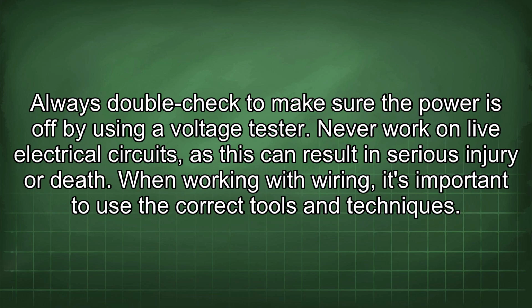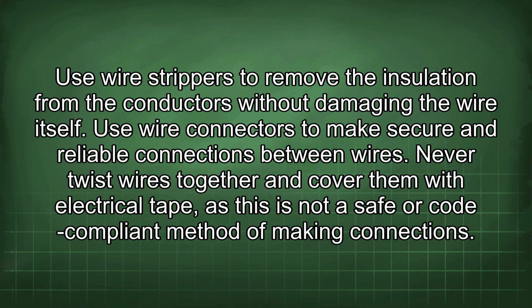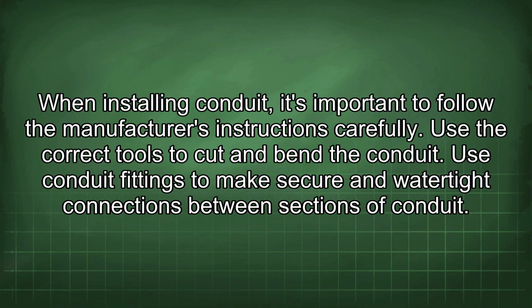When working with wiring, it's important to use the correct tools and techniques. Use wire strippers to remove the insulation from the conductors without damaging the wire itself. Use wire connectors to make secure and reliable connections between wires. Never twist wires together and cover them with electrical tape, as this is not a safe or code-compliant method of making connections. When installing conduit, it's important to follow the manufacturer's instructions carefully. Use the correct tools to cut and bend the conduit. Use conduit fittings to make secure and watertight connections between sections of conduit.